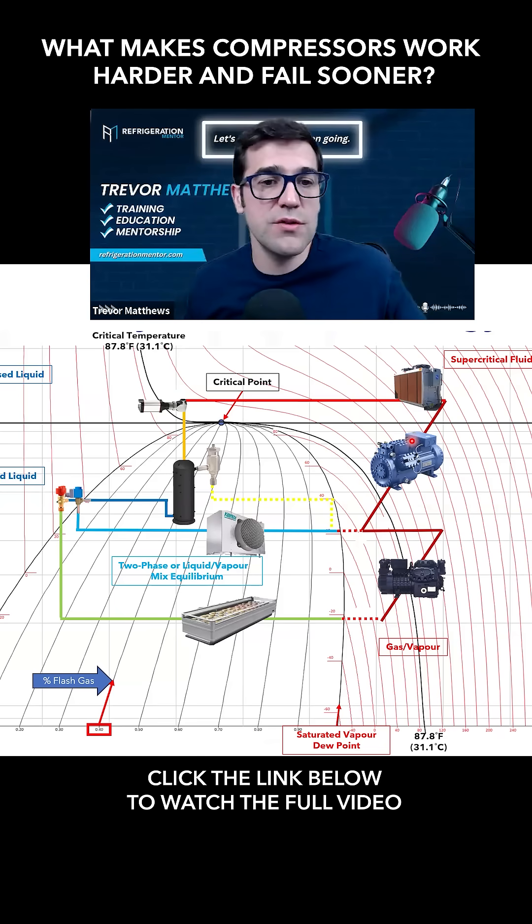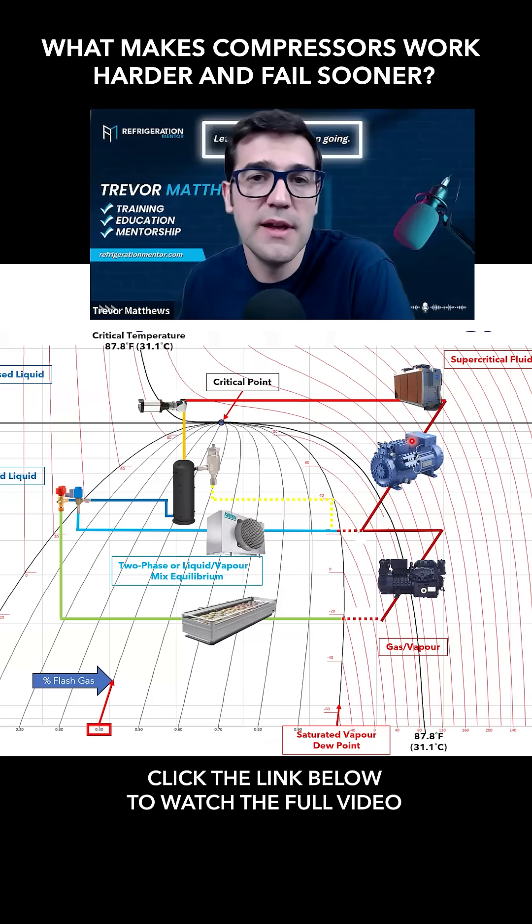But as that pressure ratio increases, it gets bigger, it's just more work, more work for those compressors. More work leads to more energy, more energy leads to higher costs. And if it's too much work, and if it's overworked, that means that now we're working the compressor in real hard to the point where now over time, it's reducing the life.